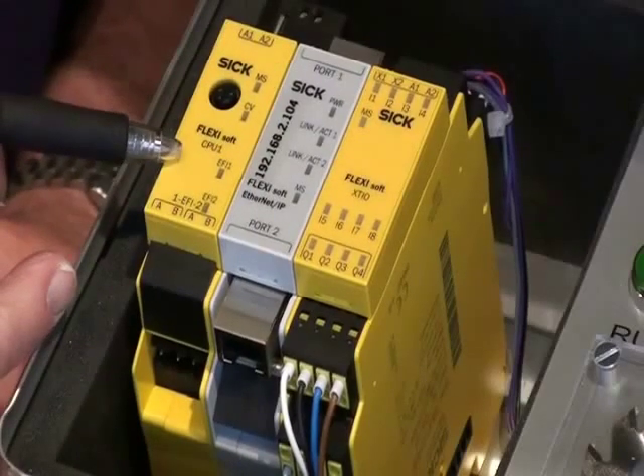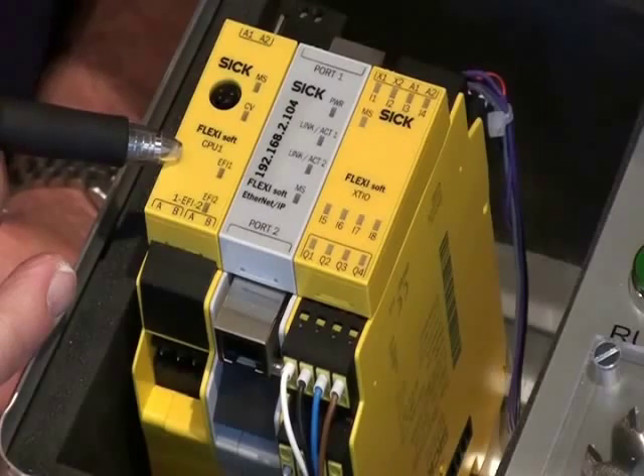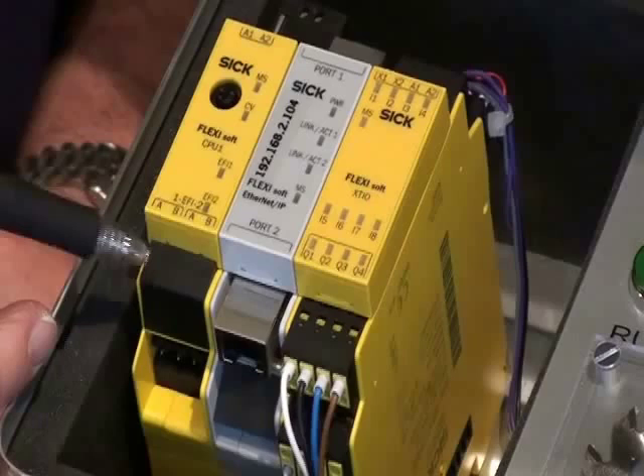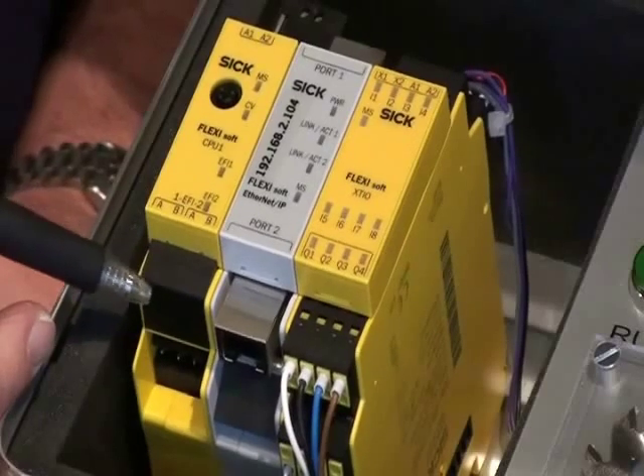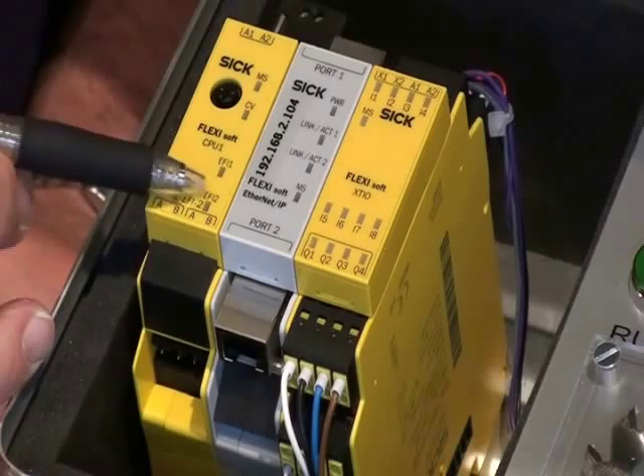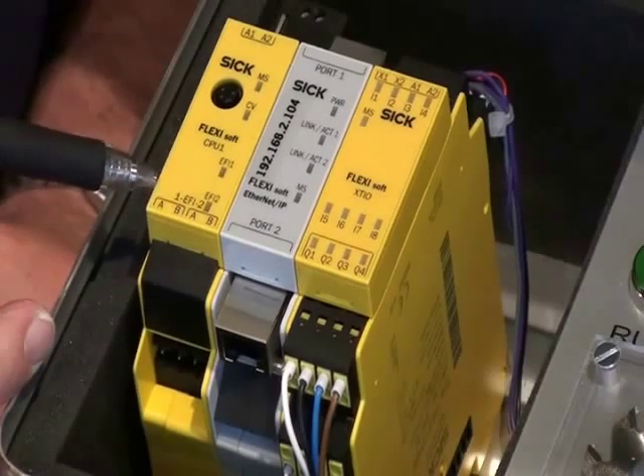The CPU modules come in two varieties: CPU 0 and CPU 1. The difference with the CPU 1 is that we have EFI connections, where we can connect our more intelligent safety devices like our S3000 scanners and some of our C4000 Advanced or M4000 Advanced light curtains.